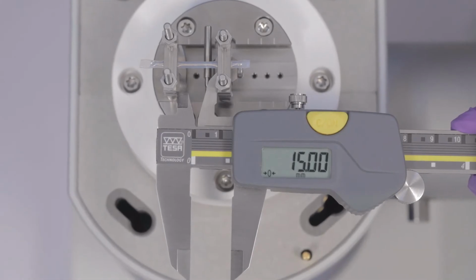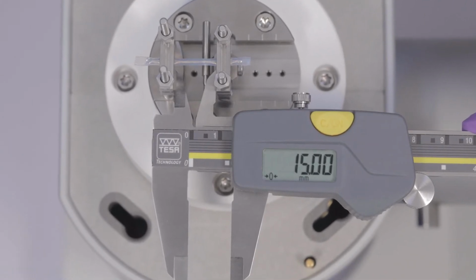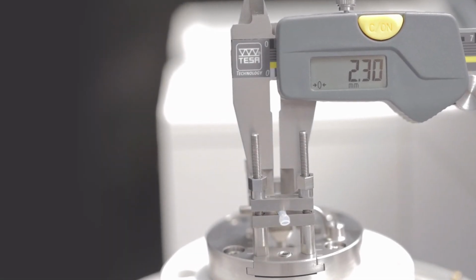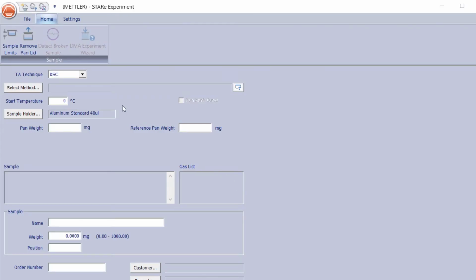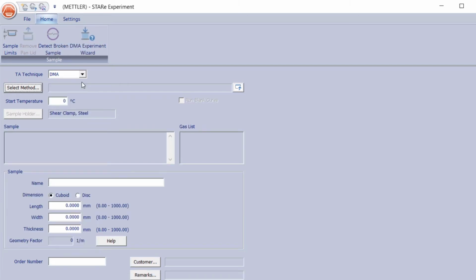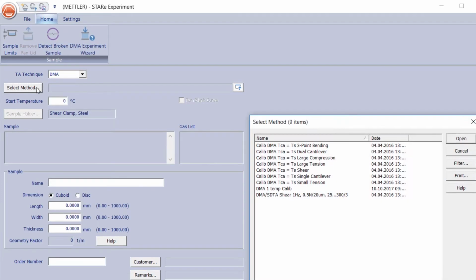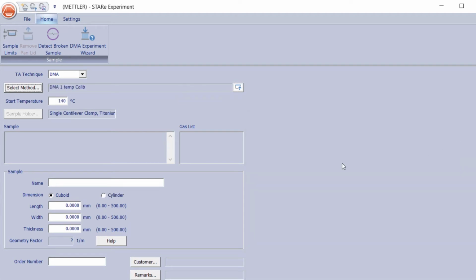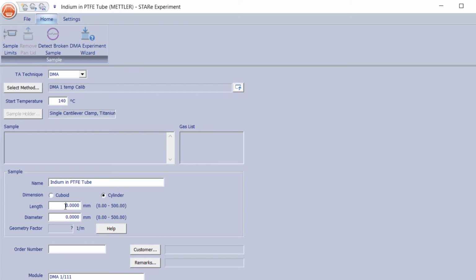Measure the free length of the sample mounted and the diameter using a vernier caliper. Note down the length and the diameter. In the experiment window of the STAR-E software, select DMA under TA Technique and the previously saved method file. Enter the sample name Indium in PTFE tube and the measured dimensions of the cylindrical sample in the corresponding box.